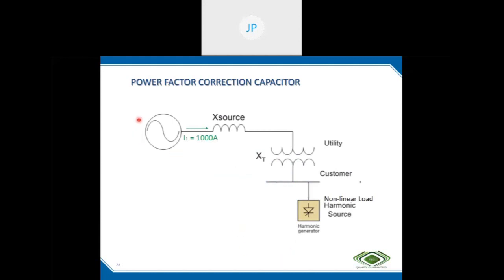Our voltage source, this is the source impedance, the transformer impedance is XT, and the bus bar and non-linear load are connected. This non-linear load is drawing a load current of 1000 amps and it is a harmonic source. No capacitor is connected to improve the power factor. So first we are considering without a capacitor, and this is the harmonic source.